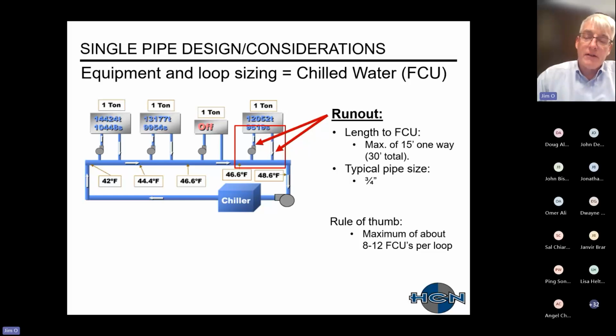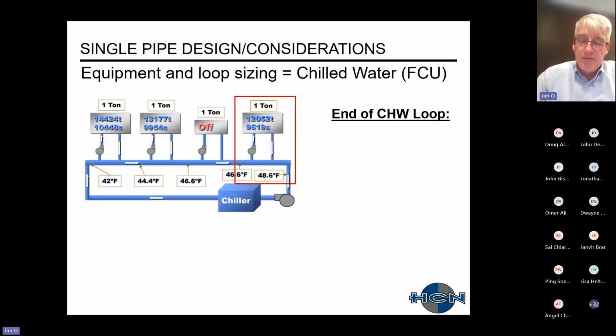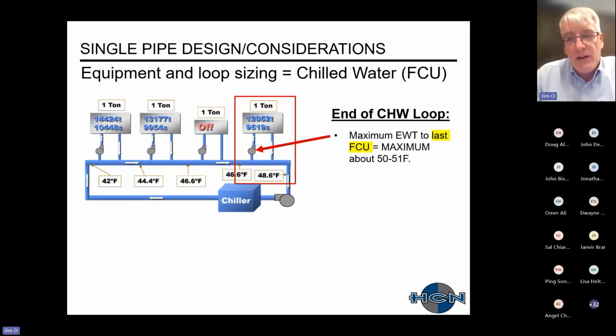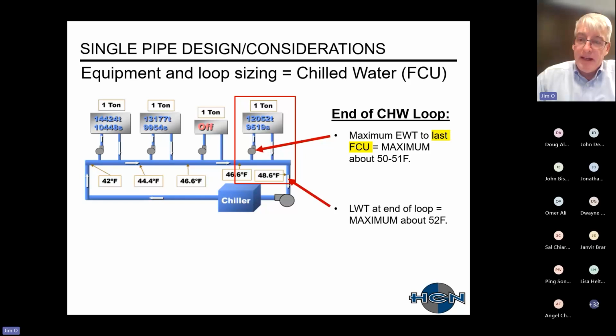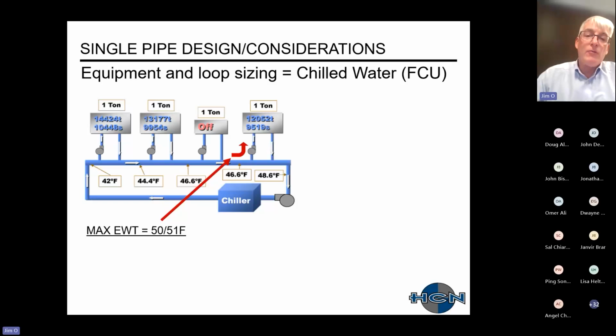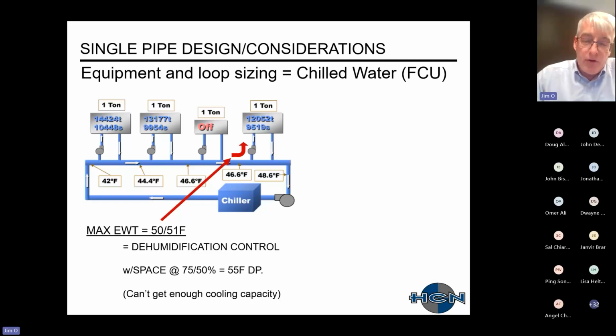In the unit shown here, it's at 48.6, but we'll talk about the end of the water being experienced by the last fan coil in the loop. So for that last fan coil, you want to basically have a maximum entering water temperature of about 50 or 51 degrees. And then at the end of the entire loop, you want to have a max of, say, 52 degrees. Now, why is this? Well, let's look at the water temperatures and then compare it to a psychrometric chart. You want to keep your entering water temperature at, say, 50 or 51 degrees because you still want to maintain dehumidification control of your fan coil or your chilled water system.